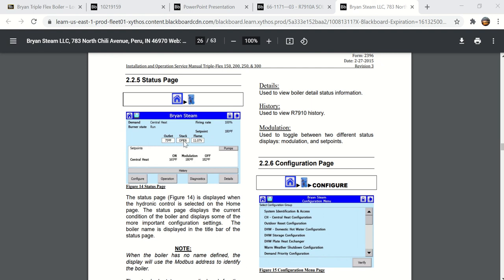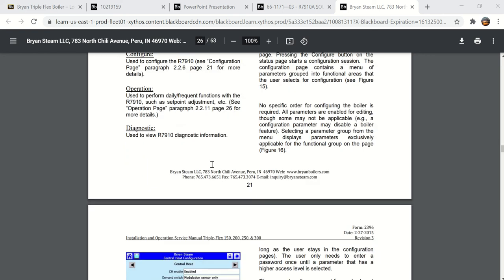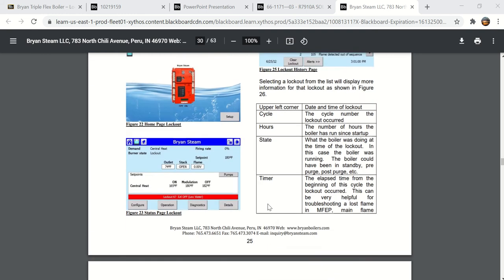actual outlet temperature of the water, the stack temperature. Obviously this one, the stack temperature sensor is not plugged in. And here is your actual flame signal. These run a flame signal from 0 to 15 volts, 15 volts being maximum. But you see across the bottom here, if you push this history bar, it'll give you fault history. I'll look at that in just a second. If you wanted to reconfigure something, you would push the configure button, the operation button, the diagnostic button, and here's some details which would tell you about the version history, things about the particular controller itself. But typically you would push the operation button here, and let's scroll down a few pages to show you what the operation screen looks like.